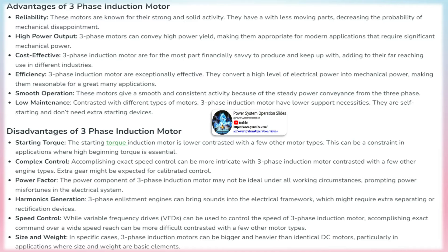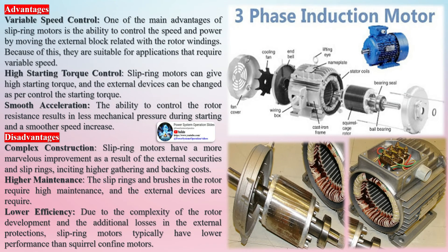One of the main advantages of slip ring motors is the ability to control speed and power by adjusting the external resistance connected to the rotor windings, making them suitable for applications that require variable speed. Slip ring motors can also provide high starting torque, and the external resistance can be adjusted to control the starting torque. The ability to control the rotor resistance results in less mechanical stress during starting and a smoother acceleration.